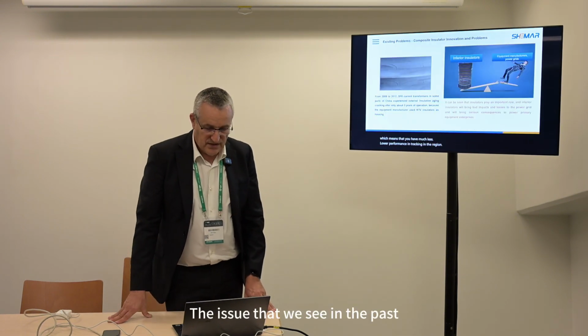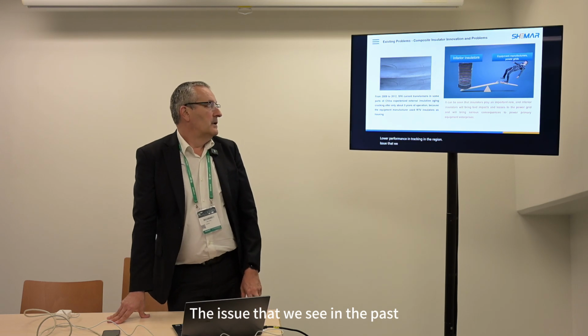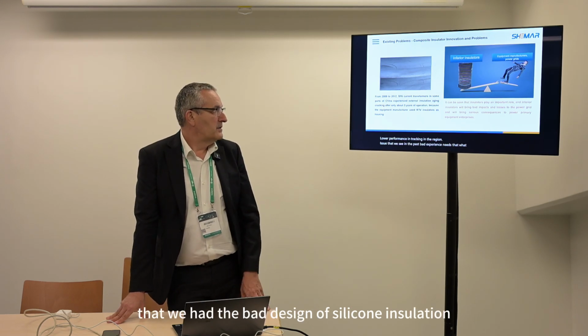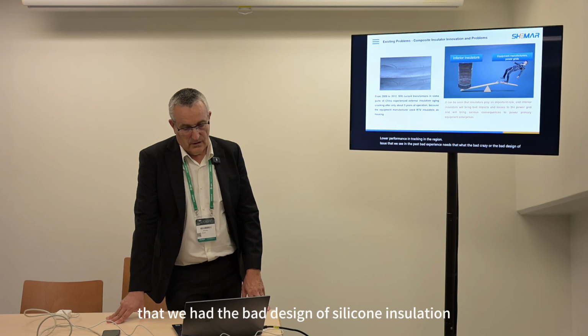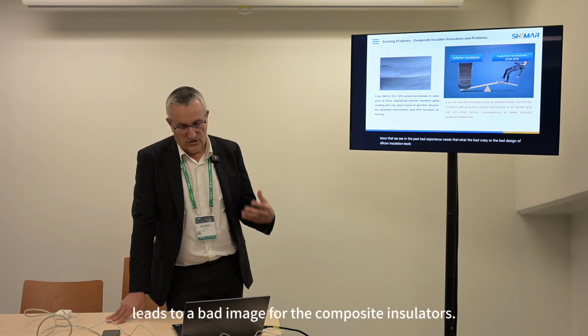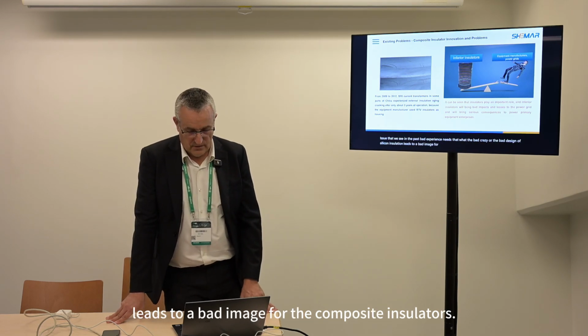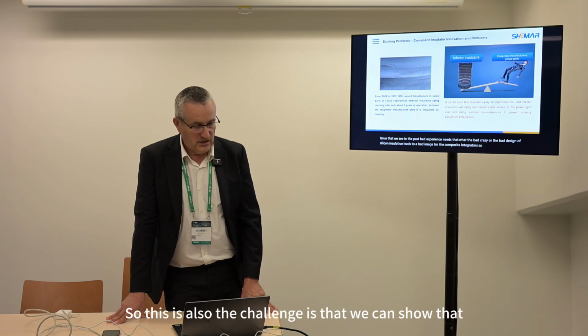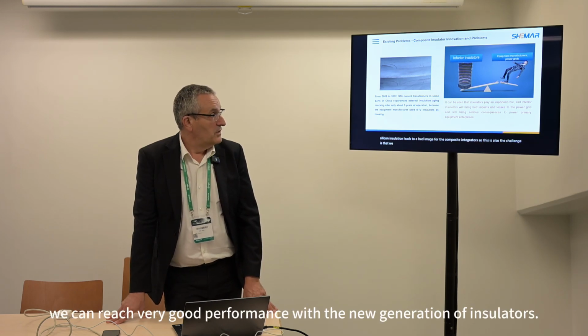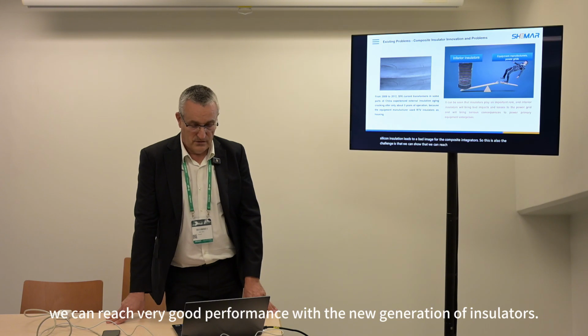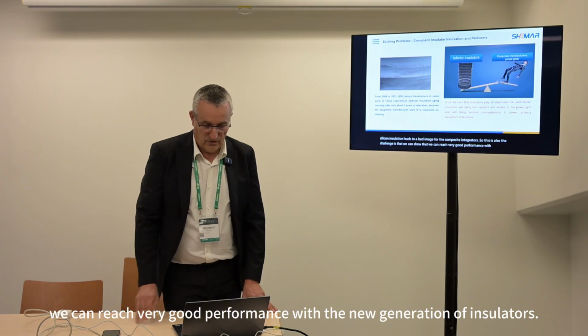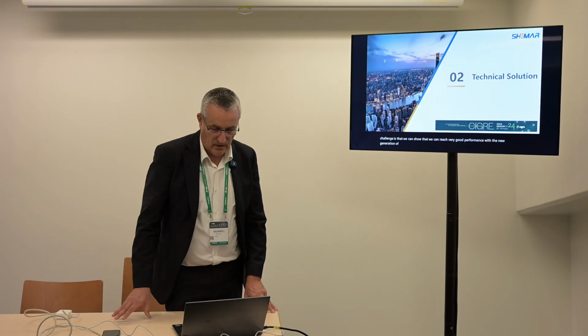The issue that we saw in the past is that bad design of silicone insulation leads to a bad image for composite insulators. So this is also the challenge: to show that we can reach very good performance with the new generation of insulators.